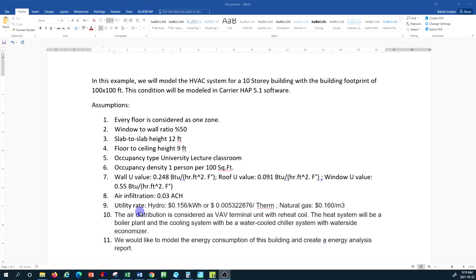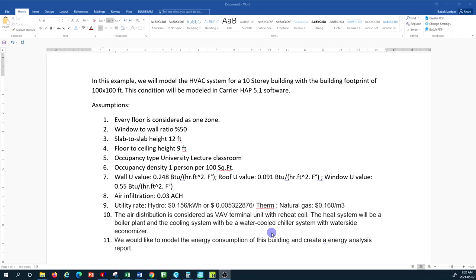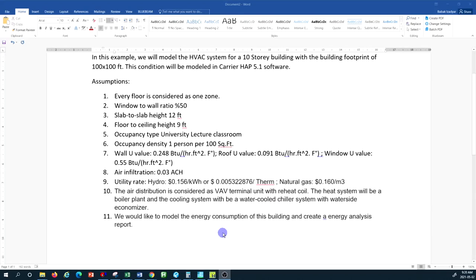For the utility rate in the local area in Canada, the hydro or electrical rate is 0.156 per kilowatt-hour, and the natural gas rate is 0.160 per cubic meter. The air distribution uses VAV terminal units with reheat coils, the heating system uses a boiler plant, and the cooling system uses a water-cooled chilled water system with a water-side economizer.